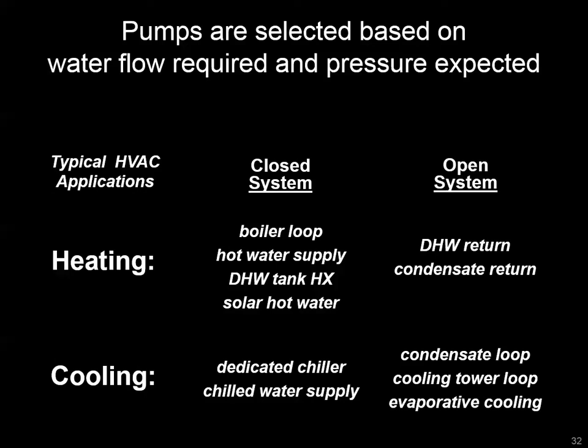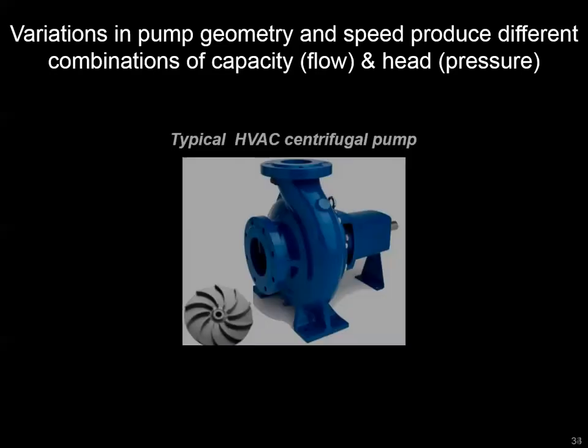There are many varieties of pump and flow combinations because there are many applications. Heating and cooling is really just a difference in the heat load from a flow standpoint. From a pressure standpoint, we can differentiate between closed and open systems. Closed systems don't deal with elevation head — the pump only needs to overcome friction losses. In an open system, the water loop interacts with the atmosphere, so the pump must also provide pressure against elevation head in addition to friction losses.